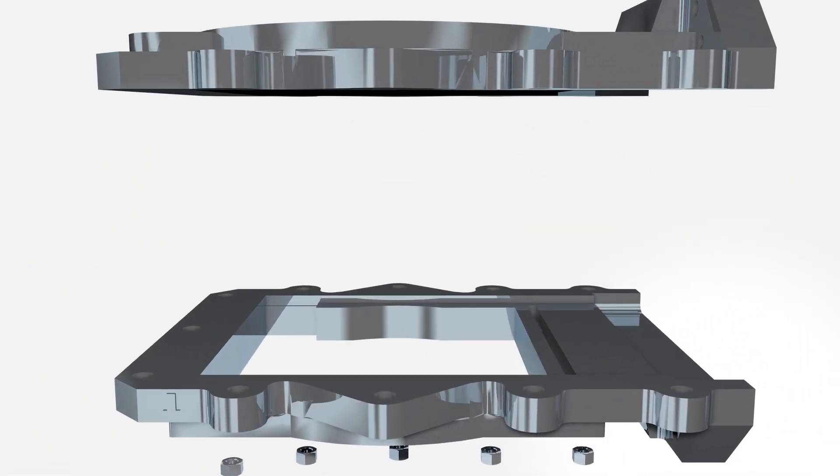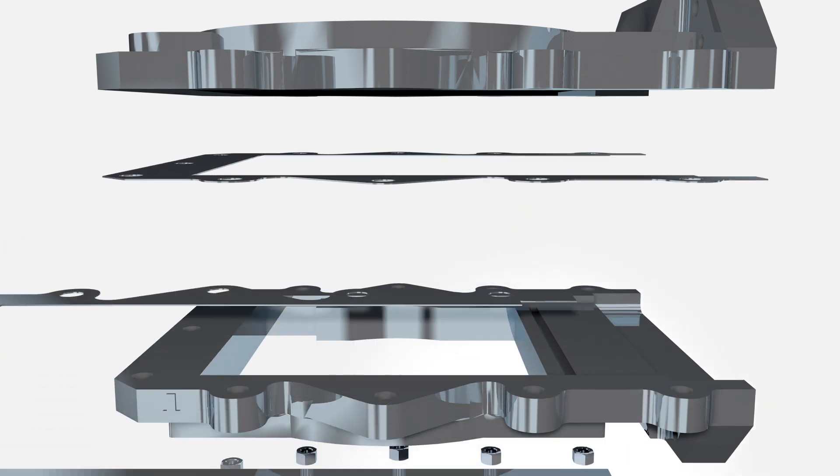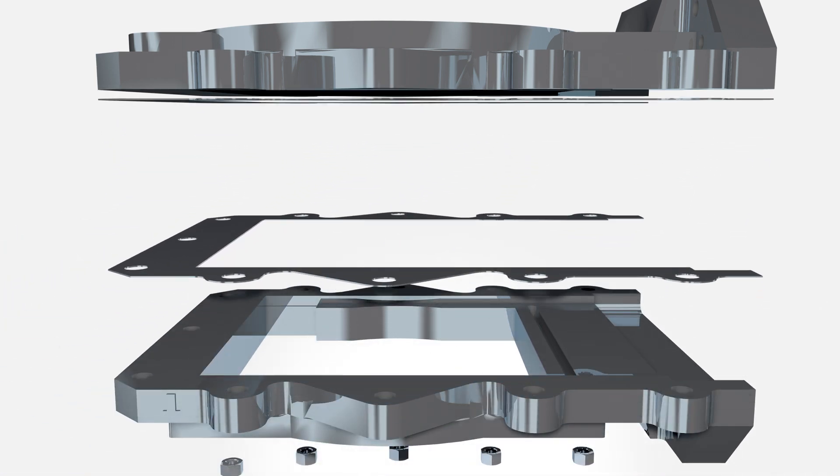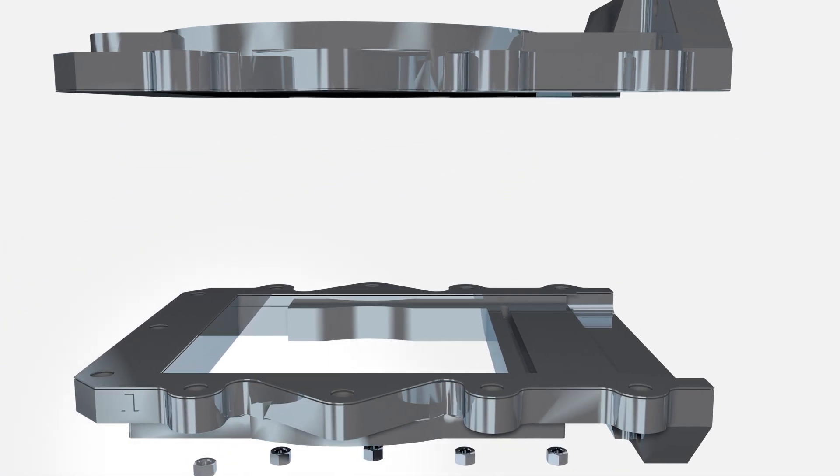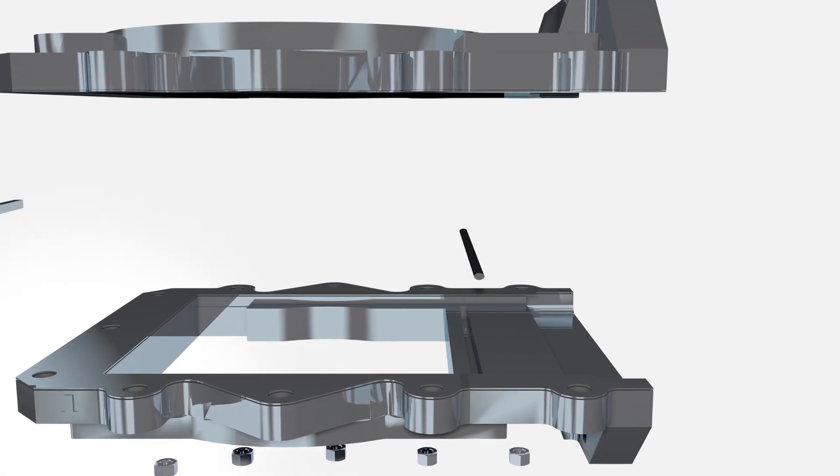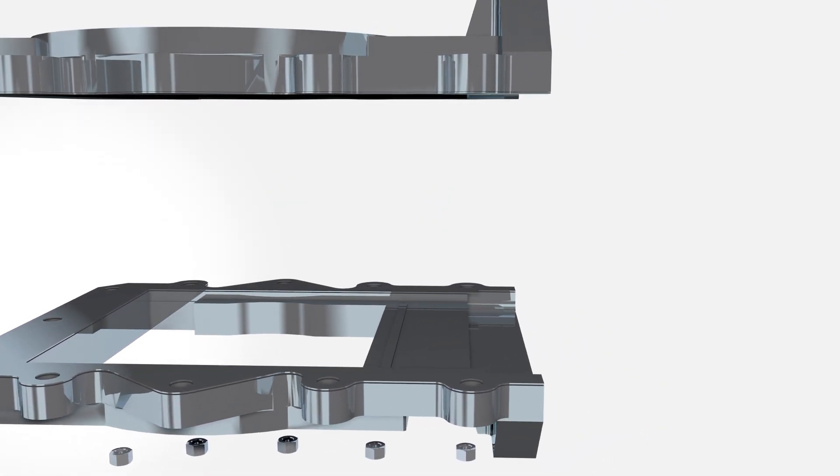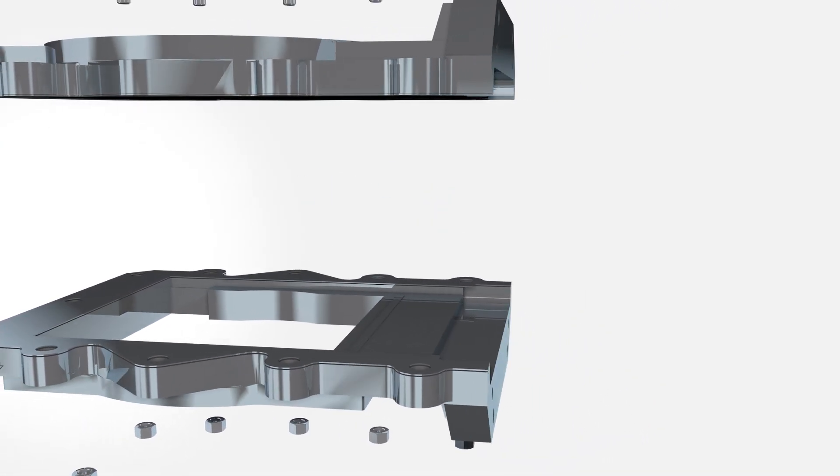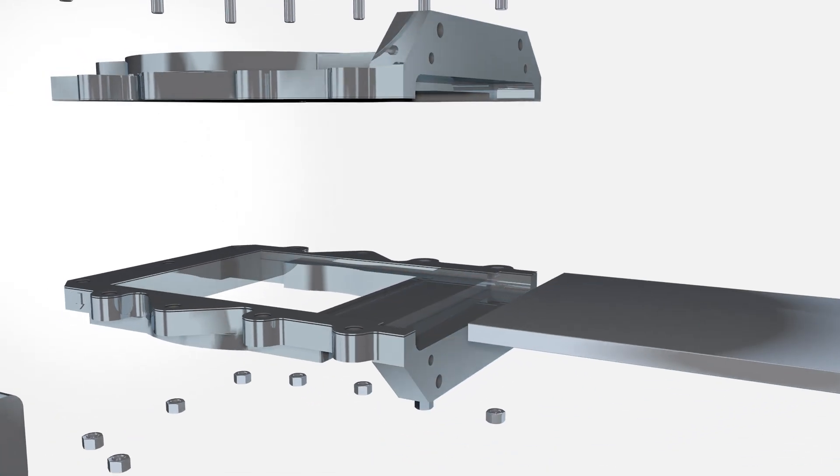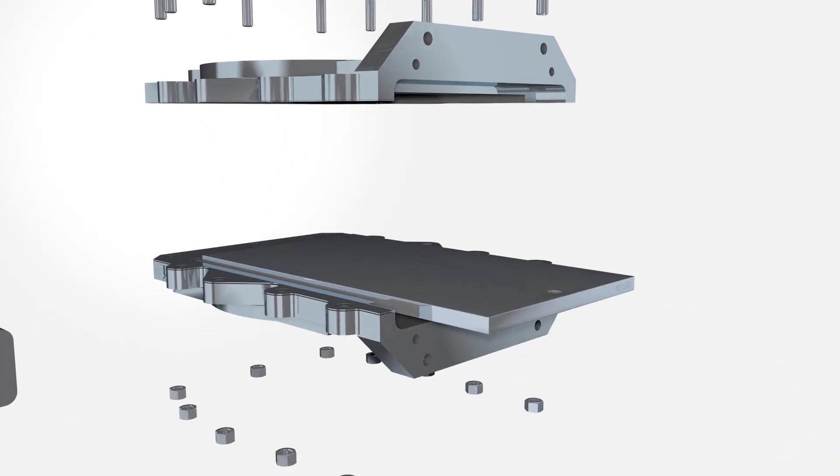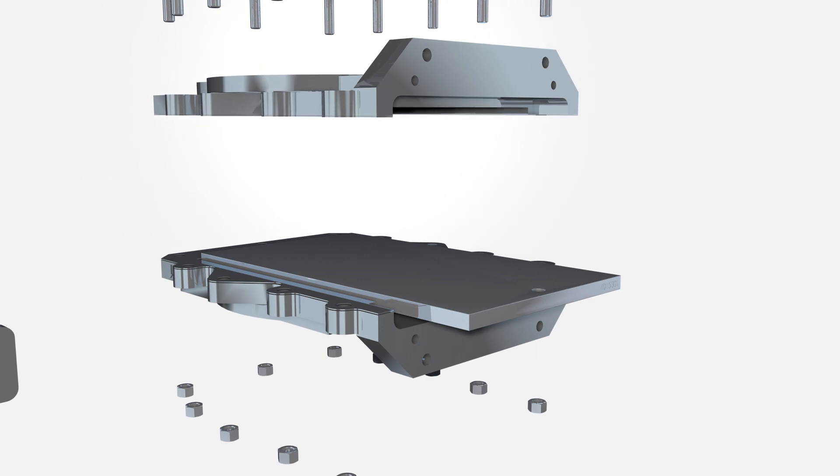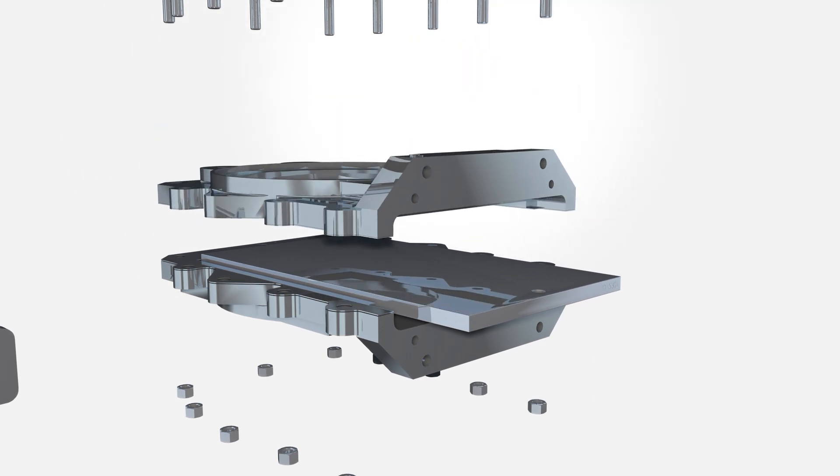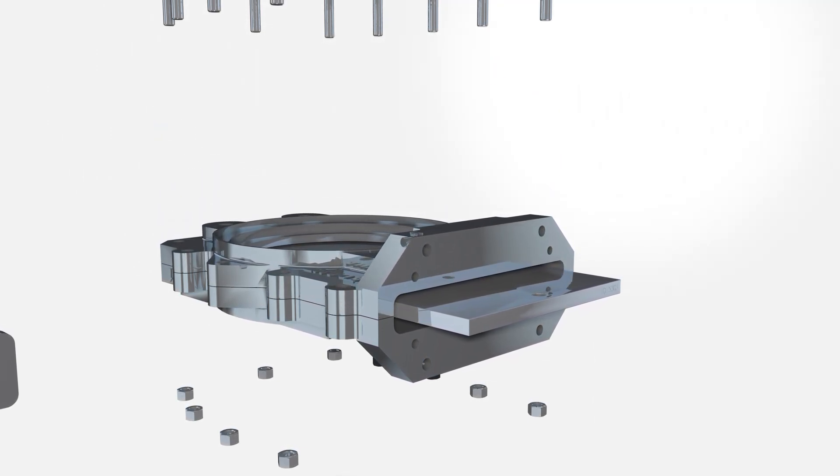Attach one of the rebuild kit's valve body gaskets onto each body half. Place the new compression cord and the scraper in the valve body's bottom half. Place the slide gate in the valve body's bottom in the fully closed position. Place the valve body's top half over the bottom half of the valve.